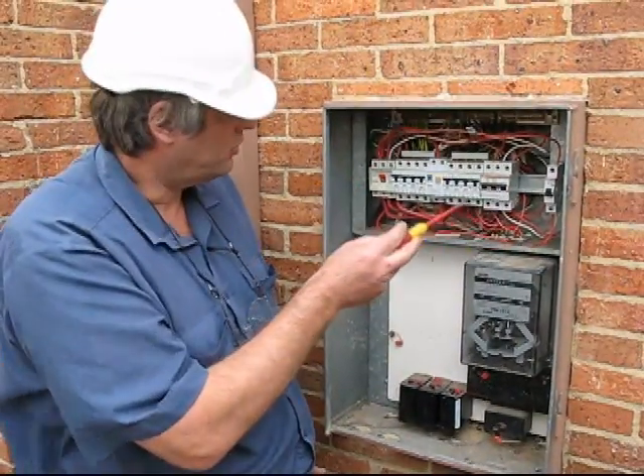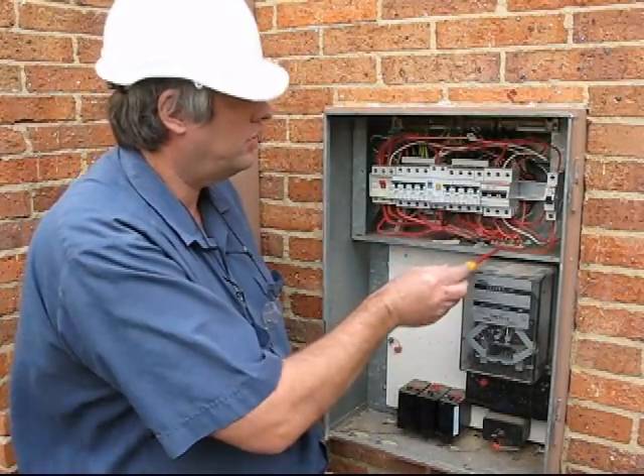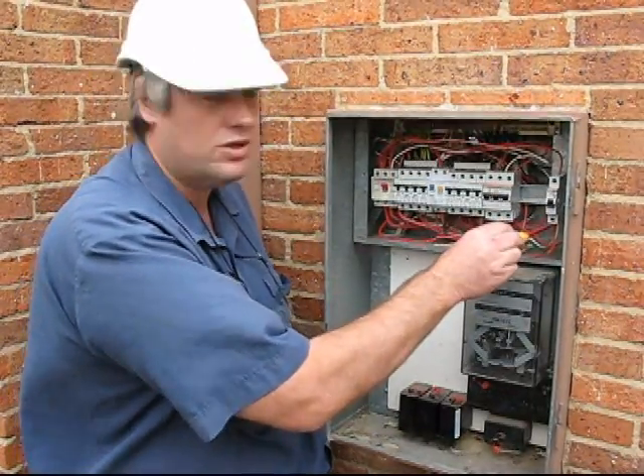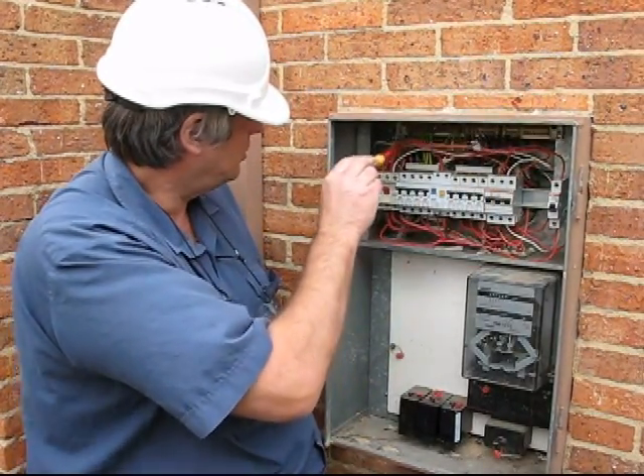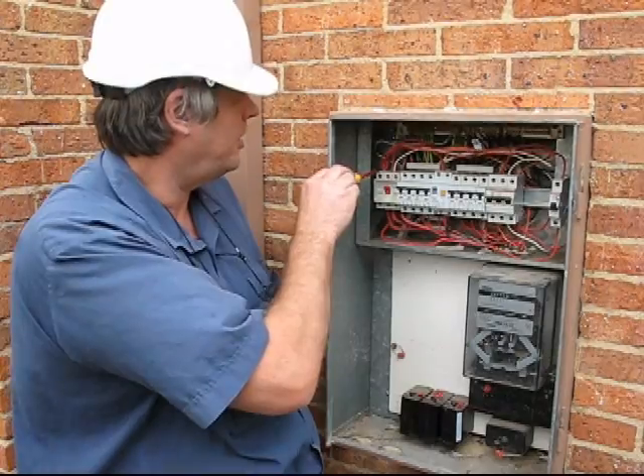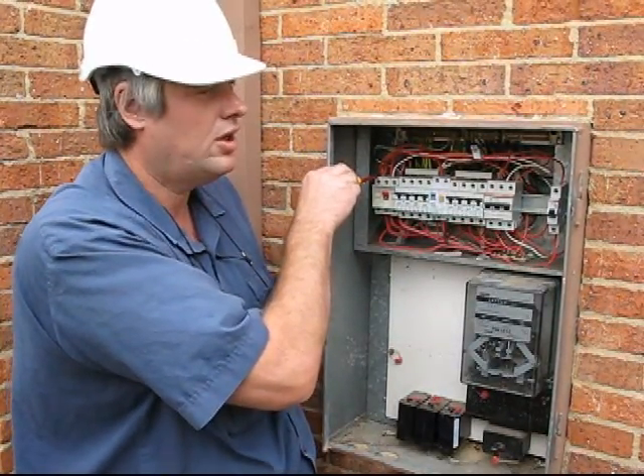With the cover off the switchboard, you can see the incoming line from the inverter to its main switch, and the outgoing into, in this case, the red phase of the three-phase main isolator on the load side.